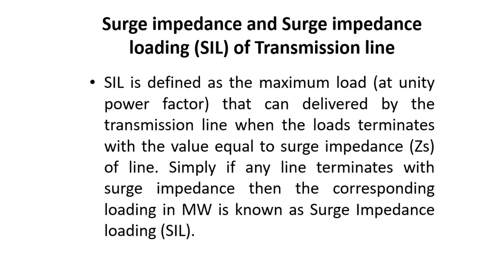So what is surge impedance? Surge impedance is the characteristic impedance of a transmission line, and it is also known as the natural impedance of the line. That's why you can see in the manual that it's written at which value of the load resistance, that load resistance is the natural load, because at that value the load resistance is equal to the impedance of the line, that is the surge impedance of the line. Now how do we find the surge impedance of the line?